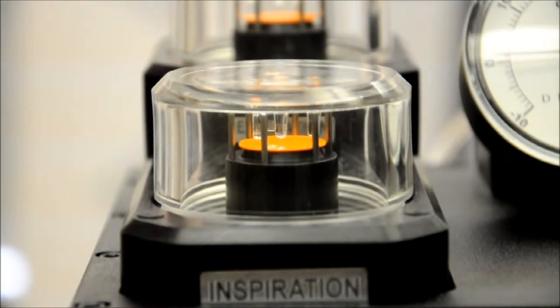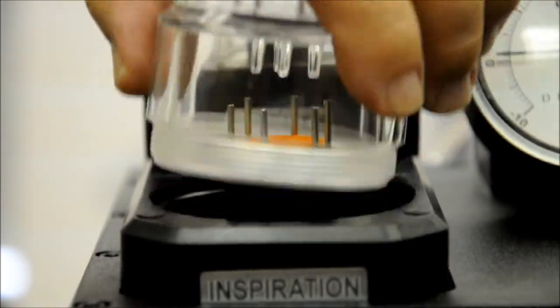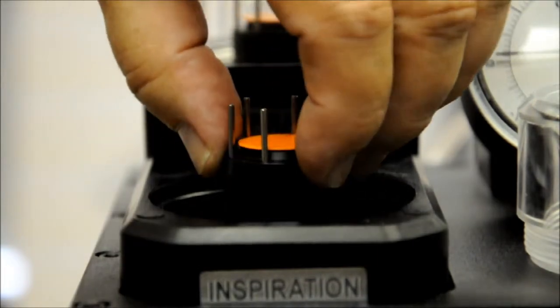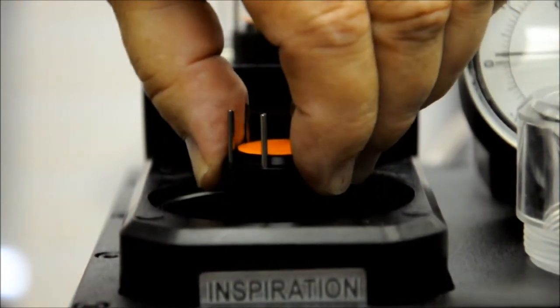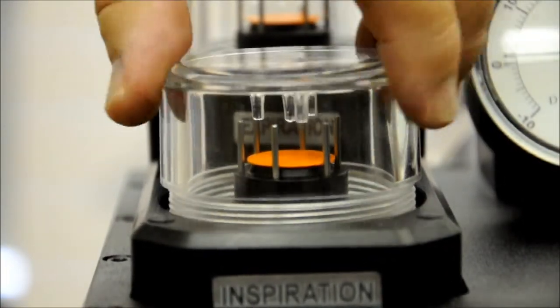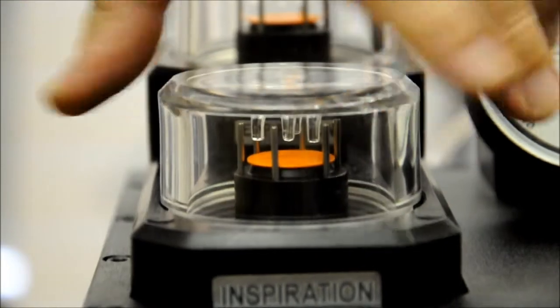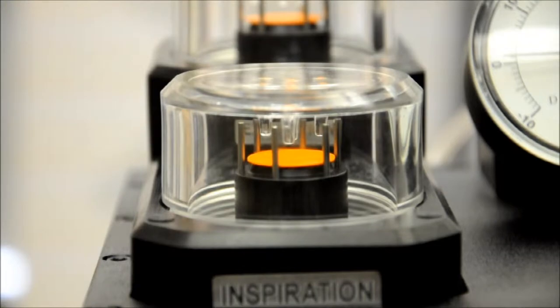This is because the seat has become dislodged. In order to reposition the seat, remove the dome and make sure that the seat is pushed in all the way. You will feel a little bit of tension as there is an o-ring being pushed through. Now when we reposition the dome you will notice how much space we have between the disc and the pins.